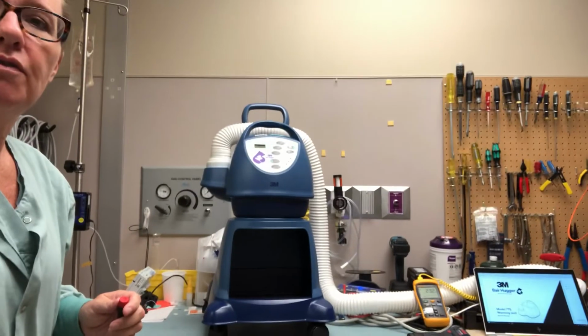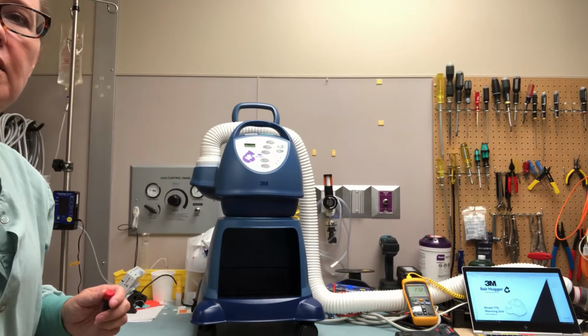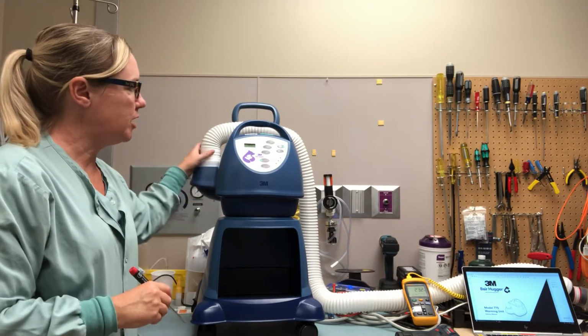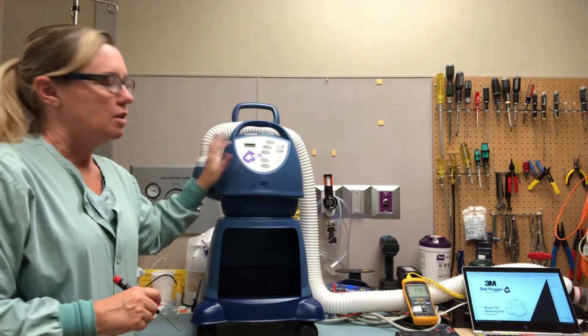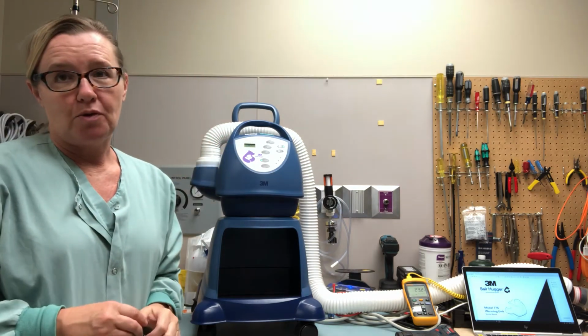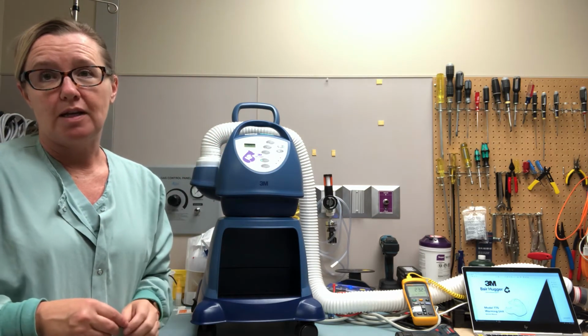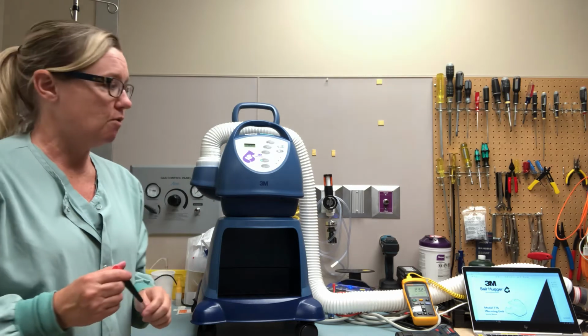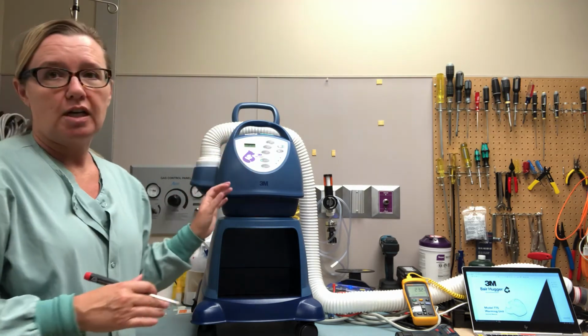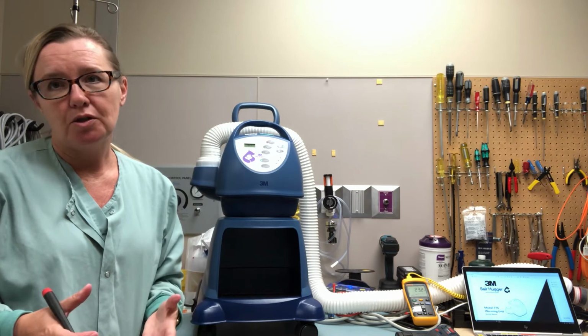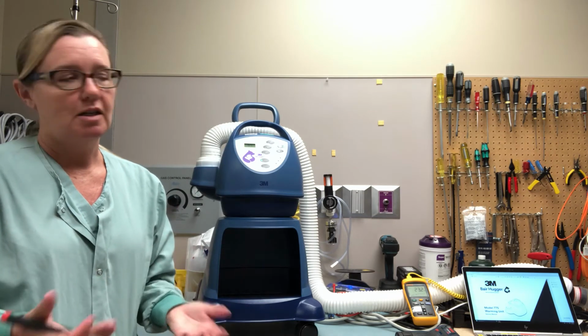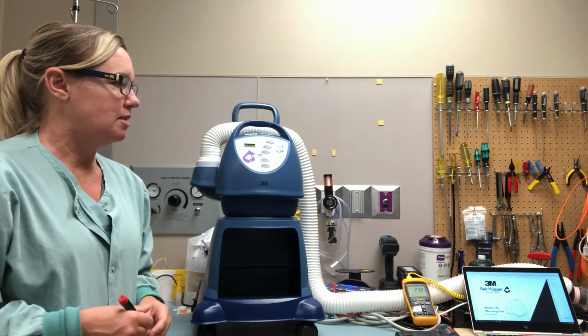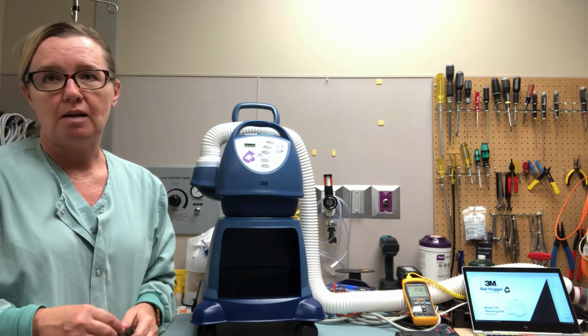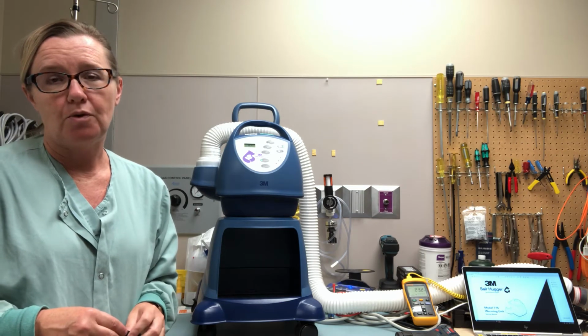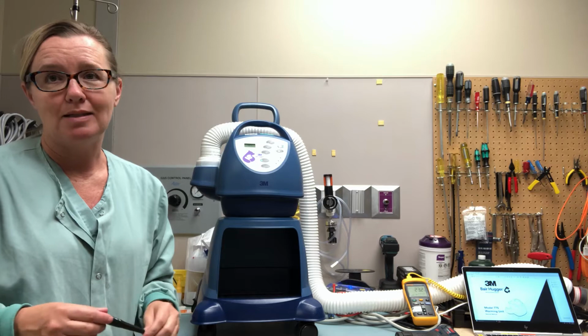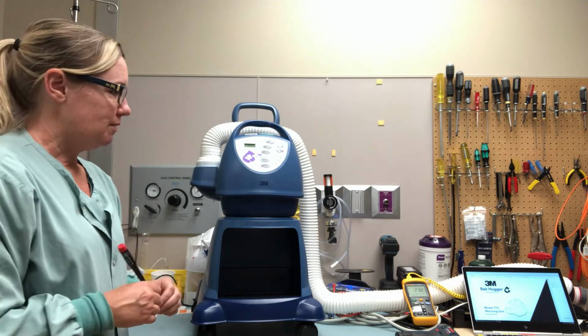It's a basic overview of the operation. So right now we have it at ambient mode. We're going to let it run for 10 minutes, wait for all the electronics to stabilize in temperature, our thermocouples to stabilize, so that way when we go in to calibrate the temperature, we can be as accurate as possible. So we'll give this 10 minutes.